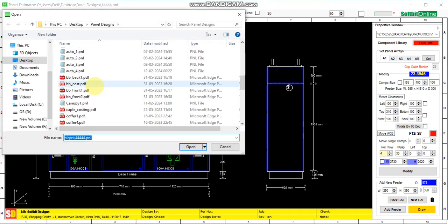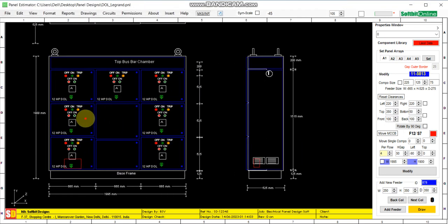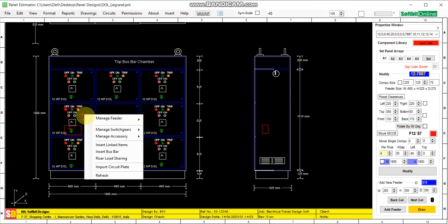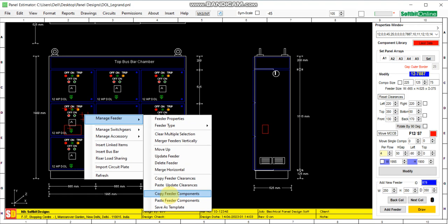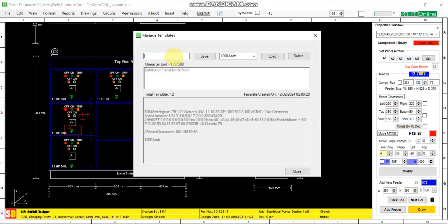Then we open another starter panel. Whether you open or remove the tree node it doesn't make any difference. You just click on the feeder you want to copy the components from and go to manage feeder, copy feeder components, template. Name it 'Dual DOL Starter — starter for water pumping station of MCD'. Save it.